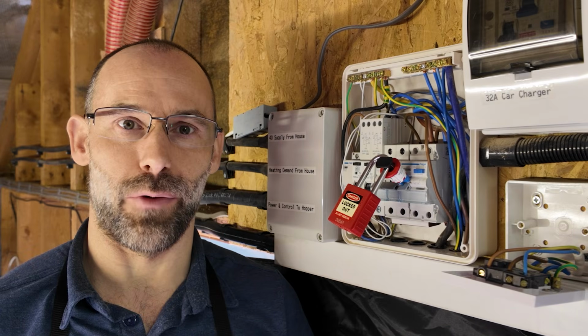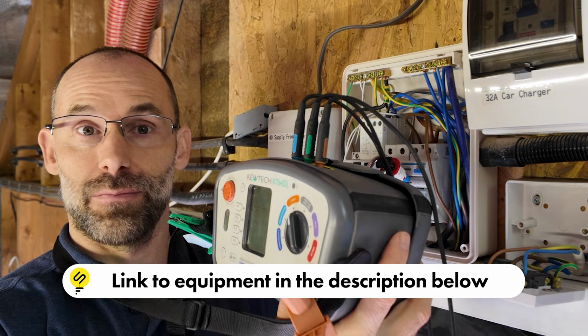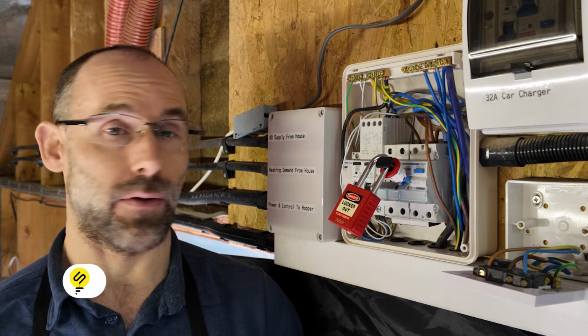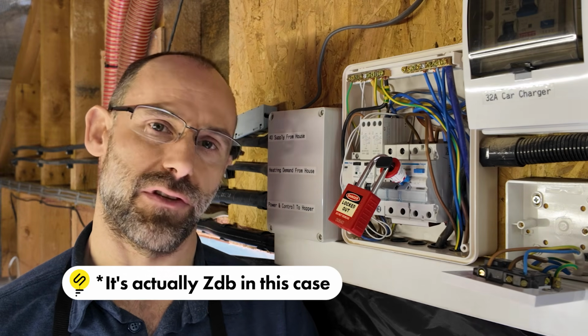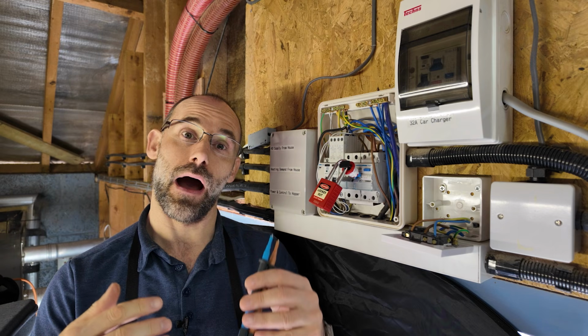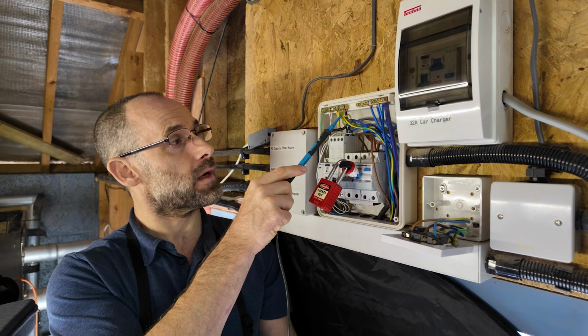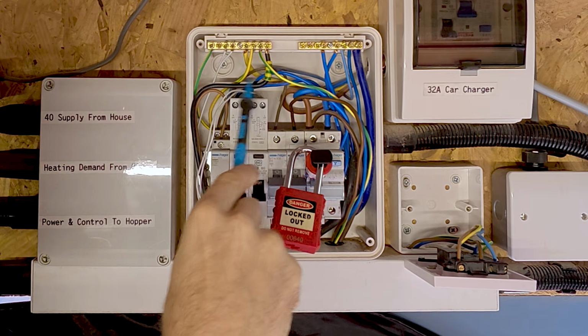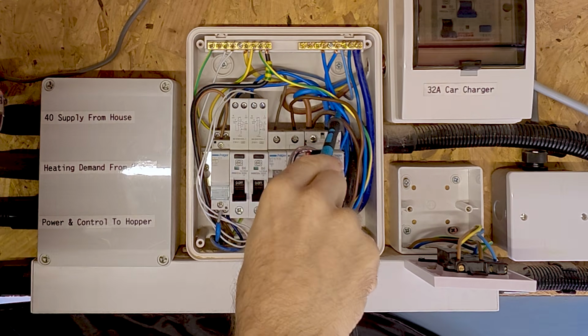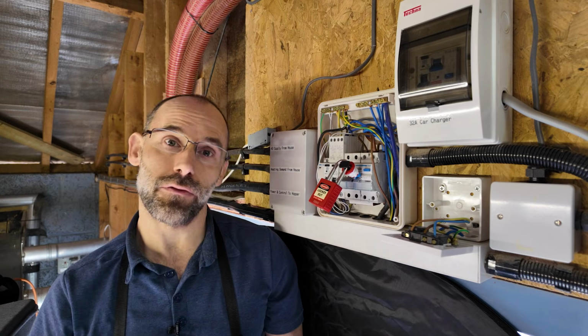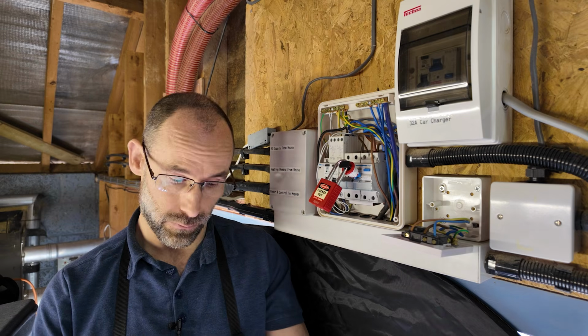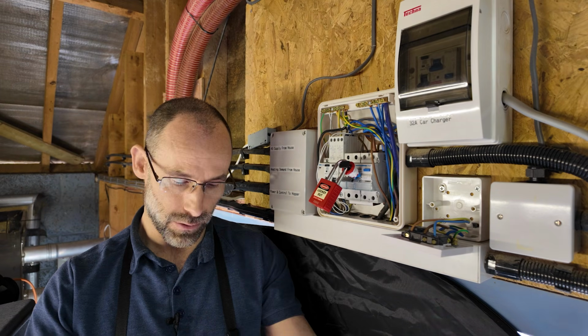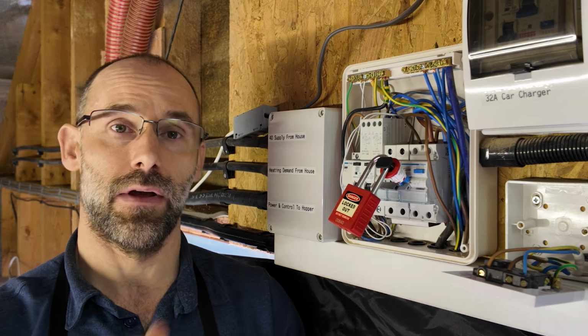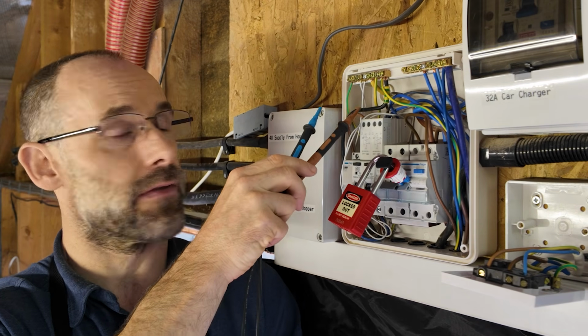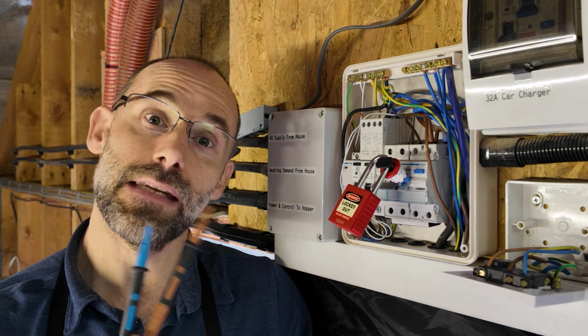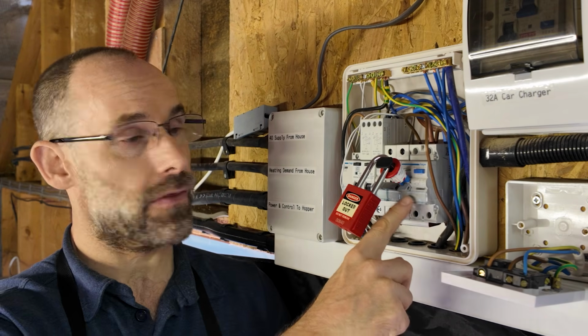This is when things get a little bit more hairy and where these 3-lead electricians multimeters really start to come into their own. What I need to test now is something called the Ze. Z stands for impedance, a bit like resistance, but more complicated. And E stands for external. So we're looking at the resistance between the earth that's coming in here from the outside to this board and the line conductor that's coming in from the outside. We want to know what the resistance of that entire loop back to the transformer outside, or wherever this goes upstream. Let's not worry ourselves about it too much. But the important thing is that the resistance is low enough that in a fault condition where current starts trying to flow down this circuit protective conductor, enough current can flow down that to trip out the residual current device.